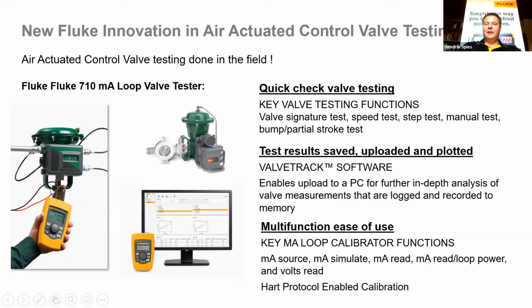So if you want to do a stroke or partial bump test, you can do that by connecting via the HART protocol, connect to the device, and then you just do your test. And there's nice software that can actually help you to do a very good report based on the OEM specification and the measurement that you've done.